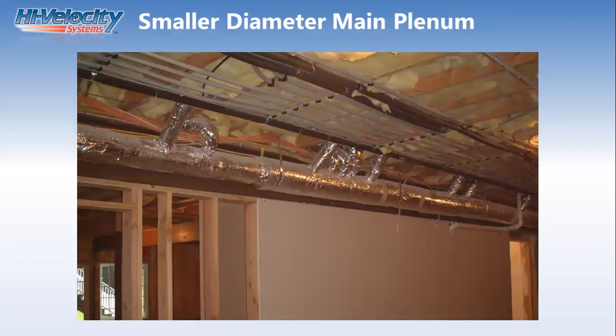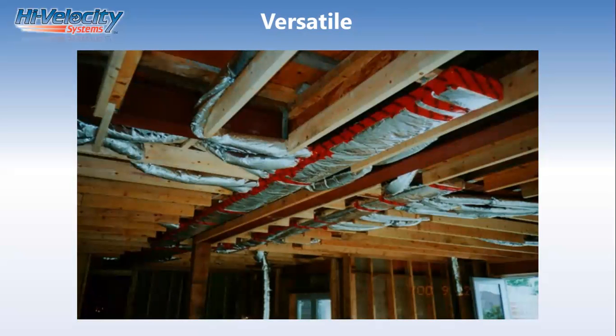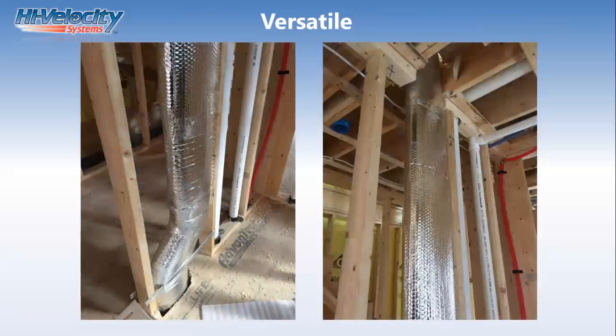The main plenum that's going to be coming off of the air handler, we would start off with either a 6-inch, 8-inch, or 10-inch diameter main metal plenum duct, which we would suggest be insulated. And that main plenum duct, the sizing will depend on the load requirement of the home and the size of the equipment that you will be installing. That round duct, 6-inch, 8-inch, and 10-inch, can be converted to a low-profile rectangular or oval ductwork if you have restrictions throughout your structure that you're trying to pass through and the round duct does not fit. You can pull out a ductulator and find an equivalent duct size to what you're dealing with, and then you're off to the races.